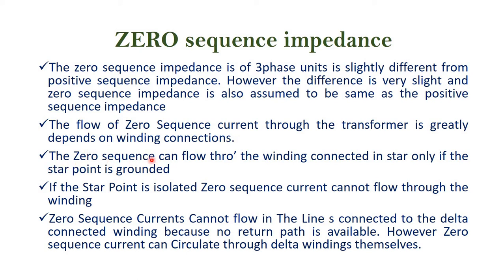The zero sequence current can flow through the winding connected in star only if the star point is grounded. If the star point is not grounded, zero sequence current cannot flow. If the star point is isolated, zero sequence current cannot flow through the winding. Zero sequence current cannot flow in the delta connected winding because no return path is available.